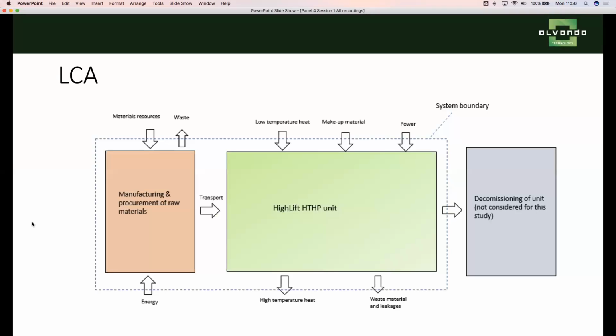Yes, so I will continue with the description of the life cycle assessment, which we carried out for the high temperature heat pump. To assess the environmental impacts, we conducted this life cycle assessment using SimaPro version 8.3. In this study, we did a cradle to grave life cycle assessment of the technology and compared it to conventional heaters like oil-fired boilers and natural gas-fired boilers. In the following figure, we can see the life cycle assessment system boundary which we used for the high temperature heat pump. It involves the construction phase, where manufacturing and procurement of raw material was involved, and then the operation phase, which is for 1 year of use. The decommissioning was not involved in this study.